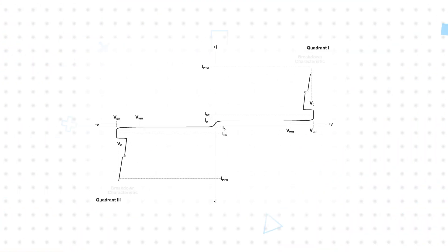Bourns' PTVS diodes operate with a foldback mechanism. After a short peak voltage, the PTVS diode clamps the voltage as it conducts current, with the clamped voltage remaining consistent even as the surge current increases.